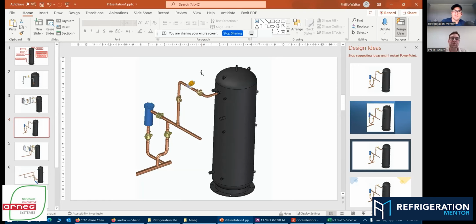So we use the valve on very low load systems, because on very low load systems we completely pump out the low temperature. A lot of small convenience stores have very low load, especially with all the great efficiency with display cases nowadays, the night curtains, lower light intensity, so less BTU per foot. So we find throughout the nighttime period, low temperature, especially with the doors, you're at holding temperature. So we pump out the low temperature system.